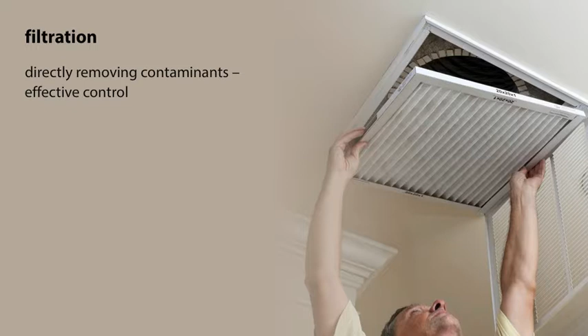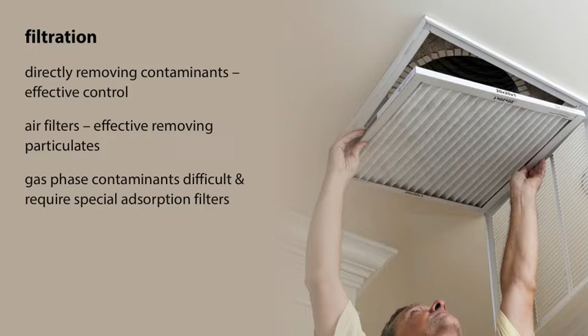Filtration. Directly removing contaminants from the air is an effective control for some contaminants. Properly selected air filters are effective in removing particulates, for example, but gas phase contaminants are more difficult and require special adsorption filters. The larger the particle, the easier it is to filter. ASHRAE has published Standard 52.2 that provides a method for testing and rating air filters. This standard enables designers to select filters for efficiency and economy based on the anticipated particle sizes for the project.